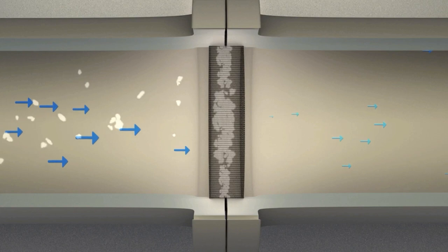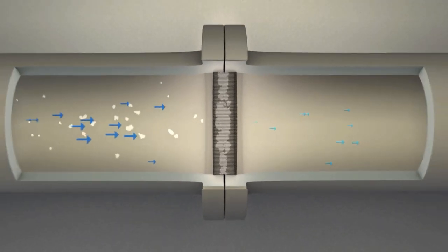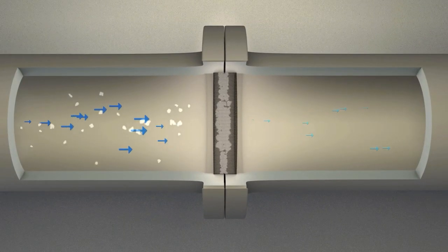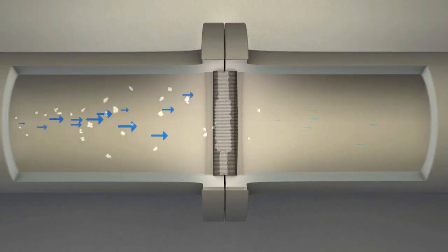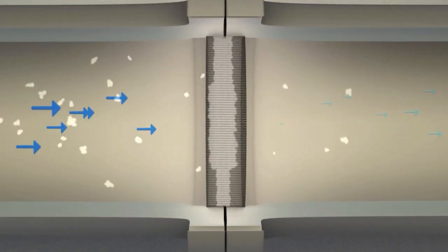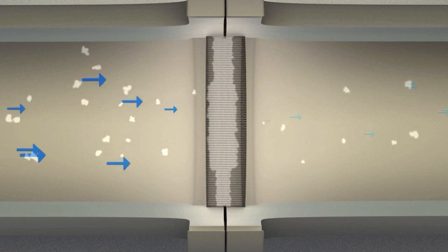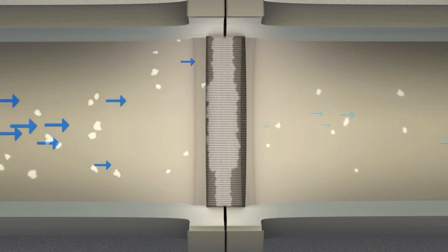Contaminants or particulates that build up in the filter will reduce media flow. As the filter becomes clogged, the downstream pressure drops. This results in an increased differential pressure, also referred to as the delta P.